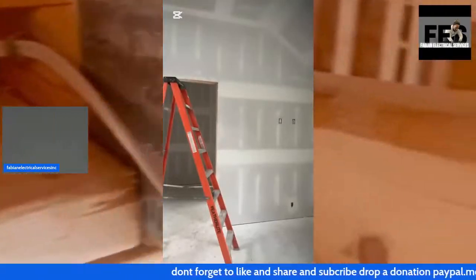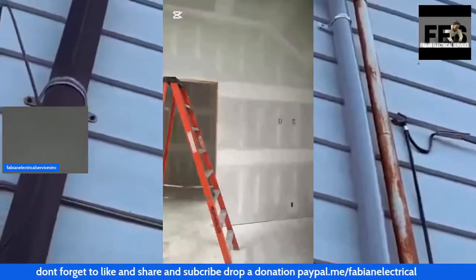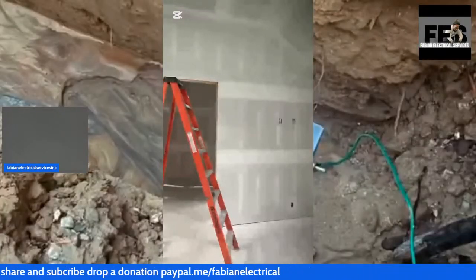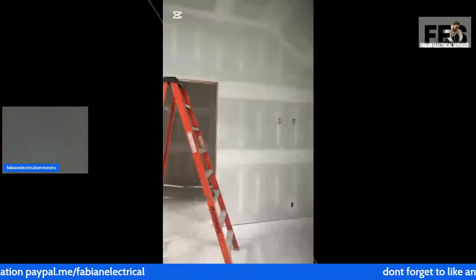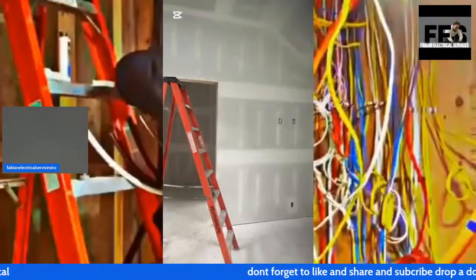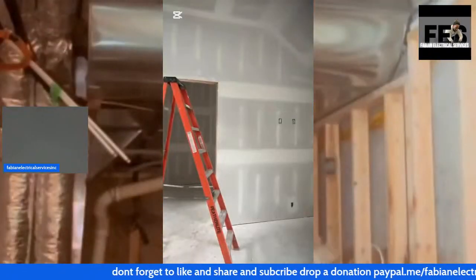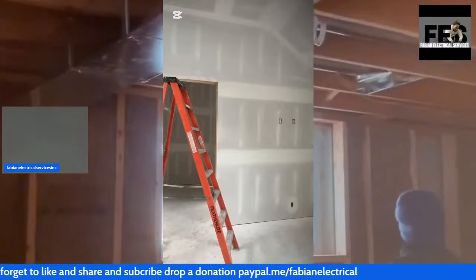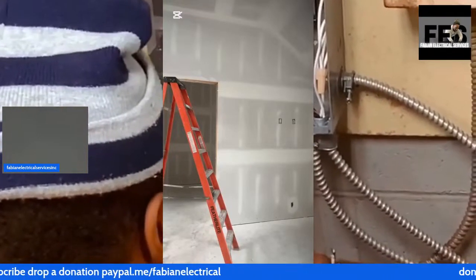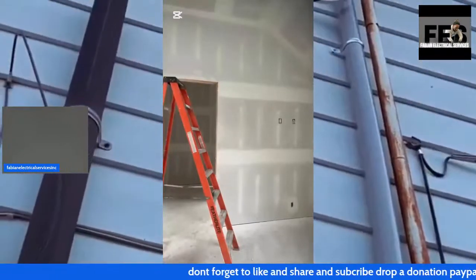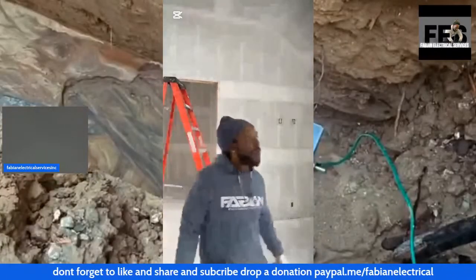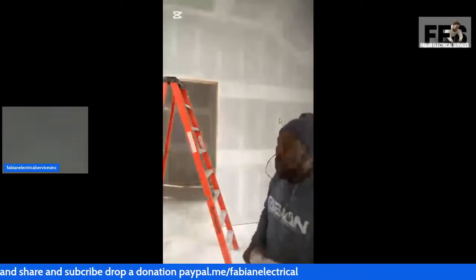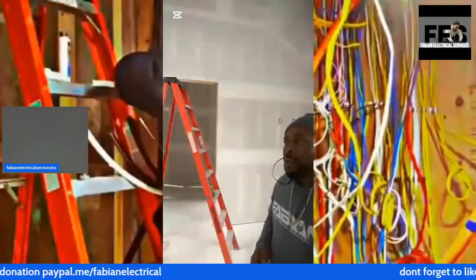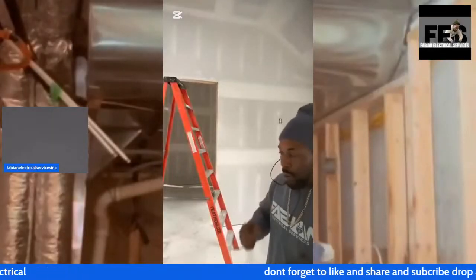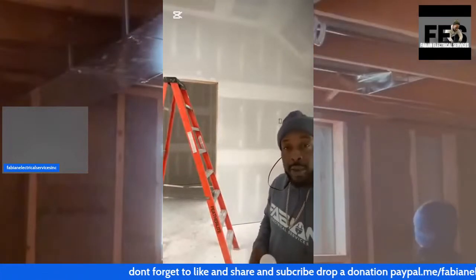When I pull my cables over, my electrical wires are already labeled, ready to go. That way, when I'm ready to land them inside the electrical panel, whether it's a 400 amp, 100 amp, or 200 amp panel, it's easy for me to just connect the wires to the breaker they need to go to. Using the wrong electrical breaker matters too - we have to make sure we have the proper breaker, and we're not putting a 30 amp breaker on a number 12 wire, for instance. You'll simply burn that wire out.